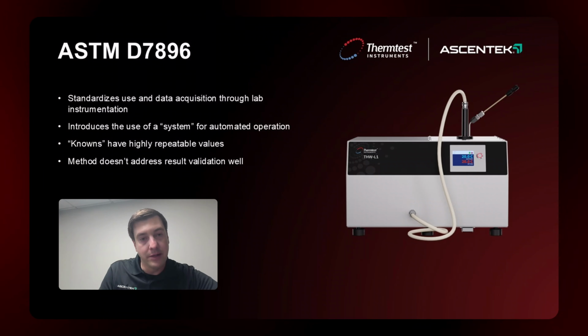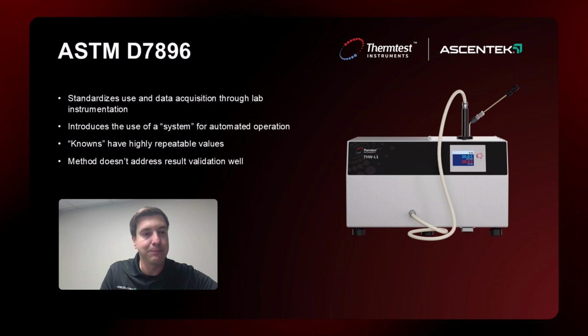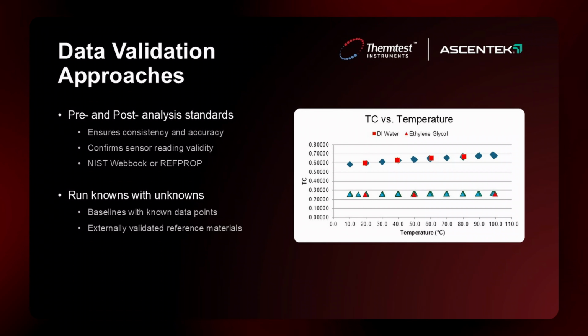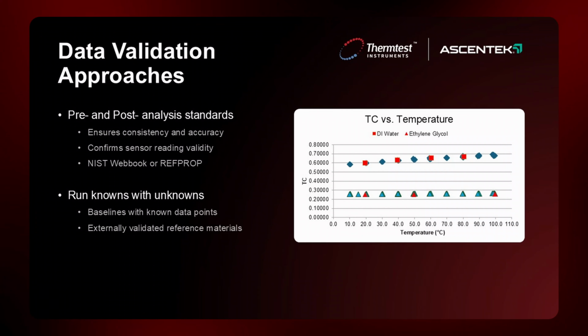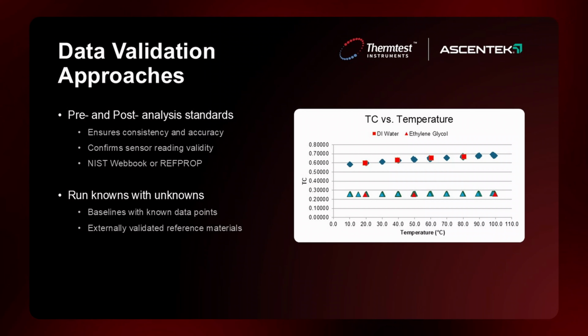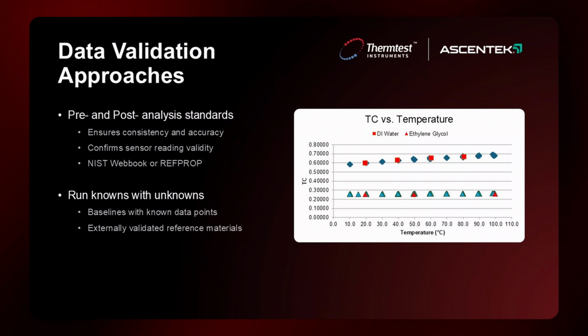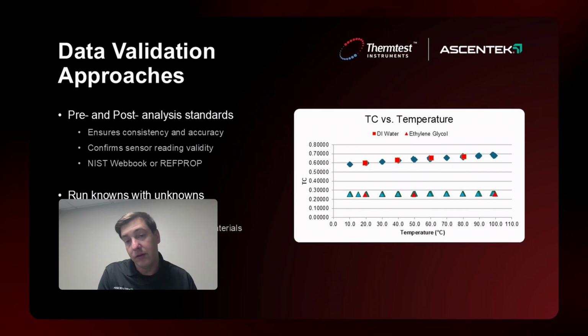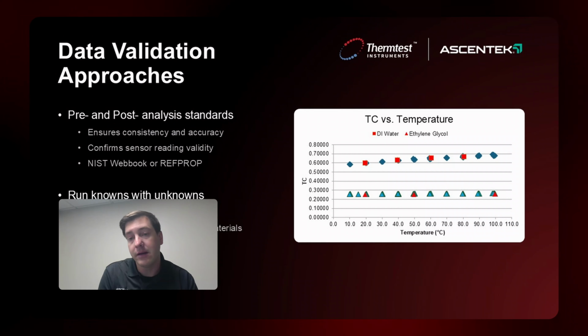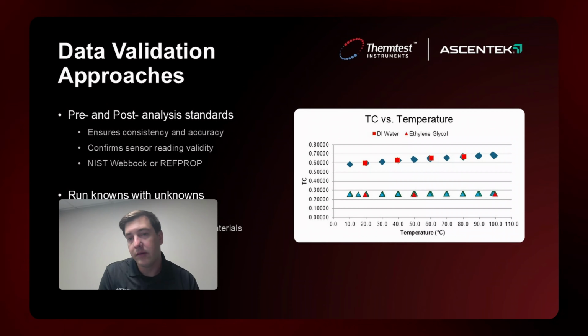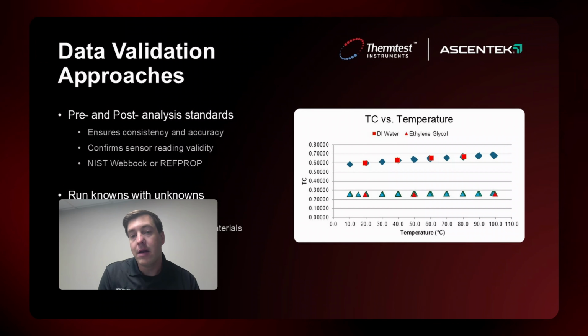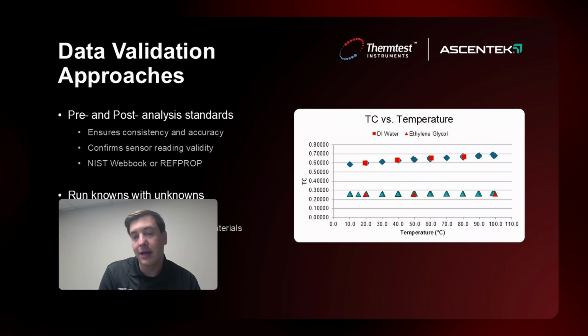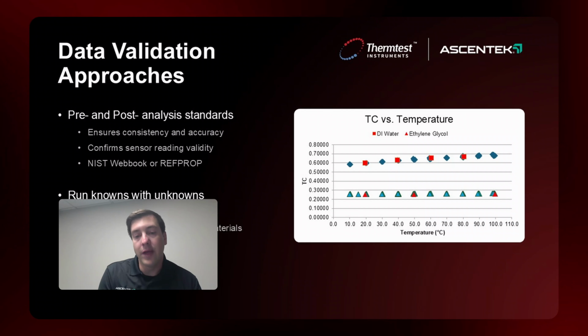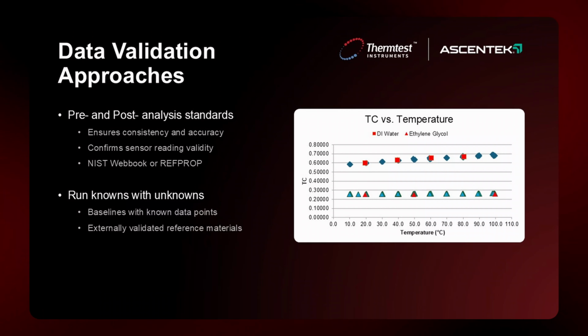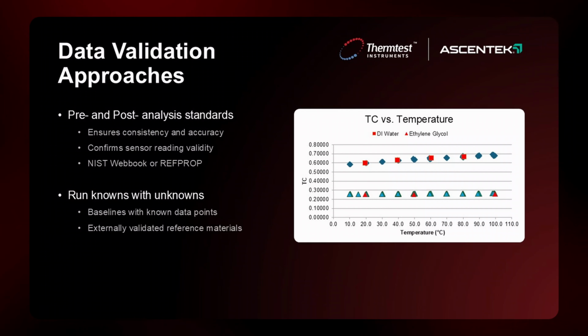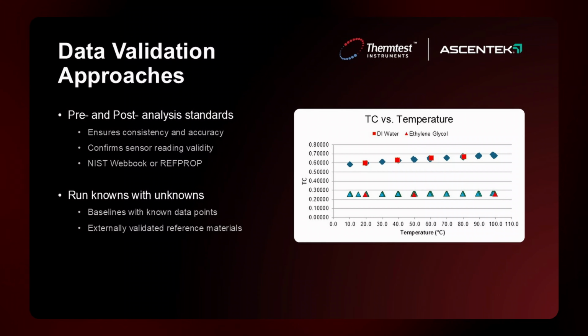So typically, what we have done is built in our own ways of doing that validation. We've basically taken two different approaches: you can do a check standard analysis, or you can run everything together. The graph you see here is what we would look at as a pre-post standard check. It's a mess of data over several runs, over several years, that we've completed on both deionized water and ethylene glycol, represented in the colored squares and triangles. The red spots are NIST identified values, what we would consider a known or accepted value for that temperature, for that fluid, for the thermal conductivity reading. So one way you can validate what you're getting is to run one of these knowns that is part of the matrix in your unknown that you are running.